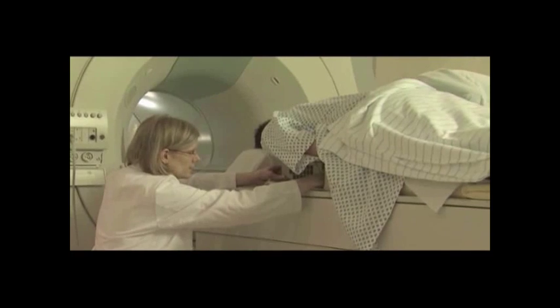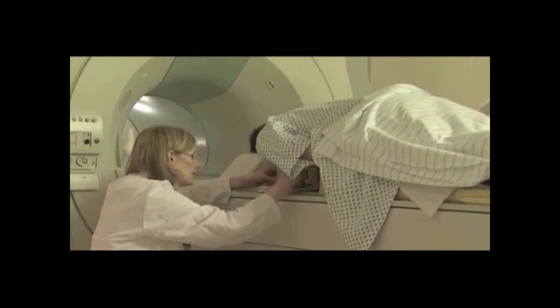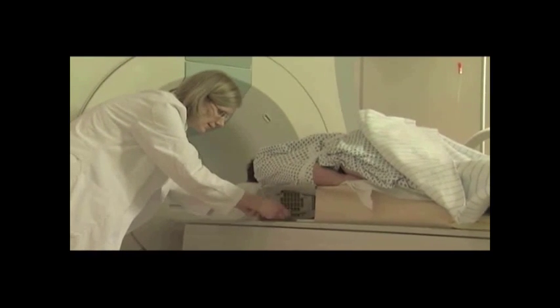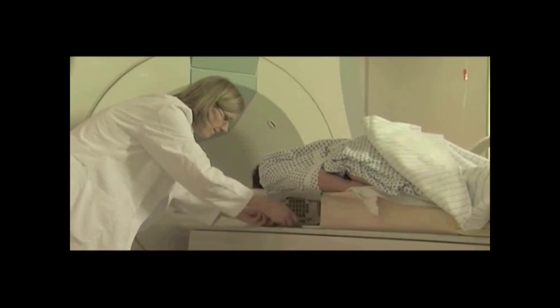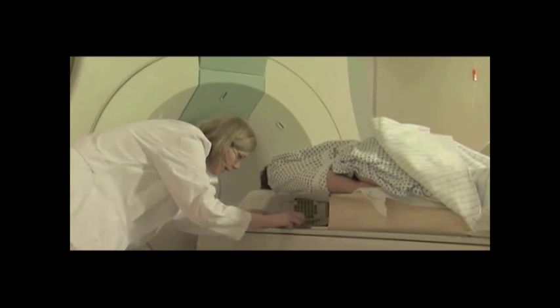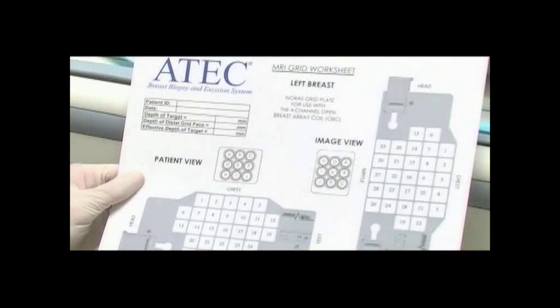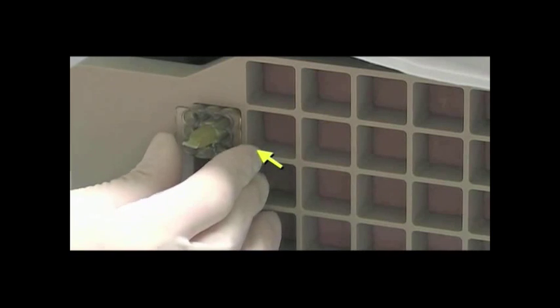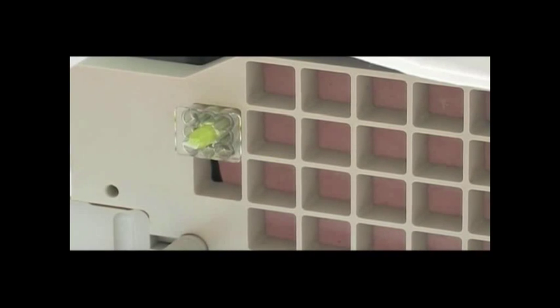Be sure the breast tissue protrudes through the immobilization plate. The skin surface should be taut in the grid space and clearly protruding. Without visibility of the plate over the area of interest, the lesion cannot be targeted. To determine target coordinates using manual calculations, a fiducial is placed into a grid space to use as a reference point before the physician begins the first scan.